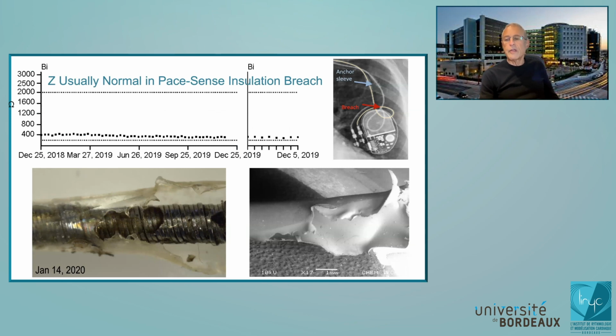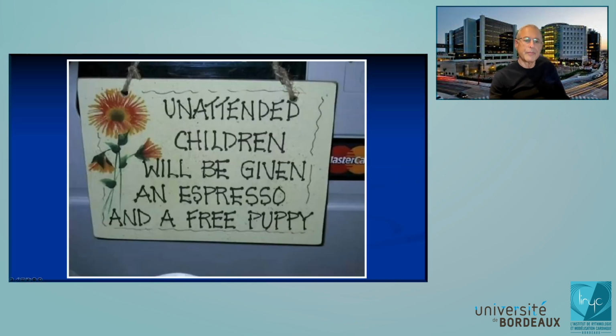Also, insulation breaches usually present, for reasons I'm not going to discuss, with normal pacing impedance. For example, here is an insulation breach in the pocket because the can is rubbing on the silicone lead and abrading it. We see the silicone is completely shredded over the conductor. We see the impedance trend is absolutely normal.